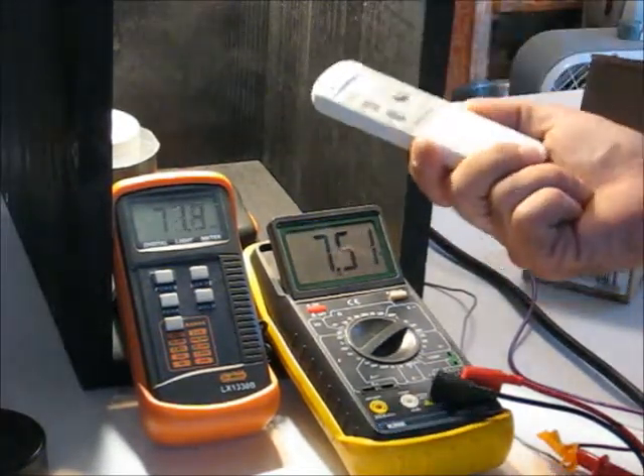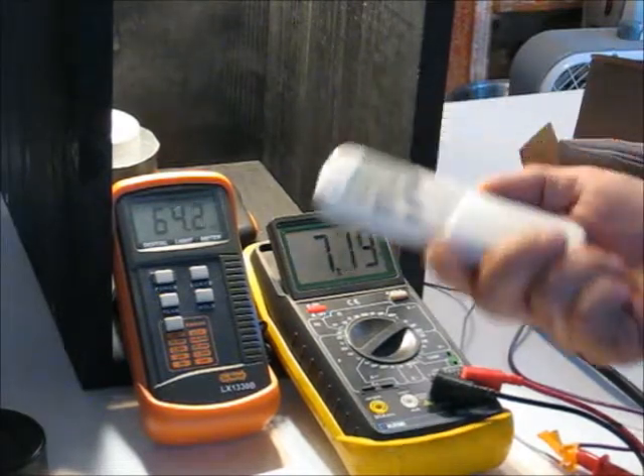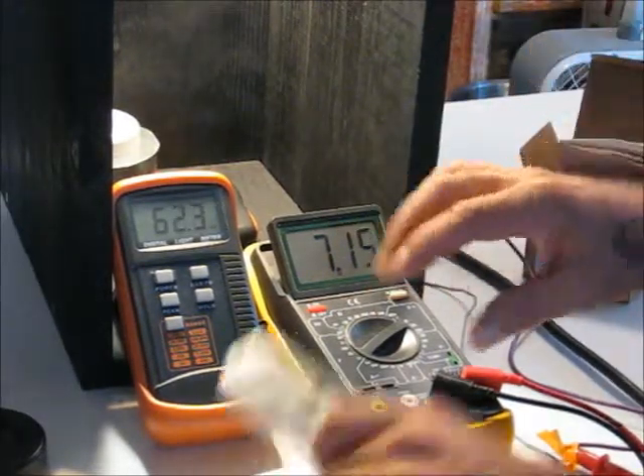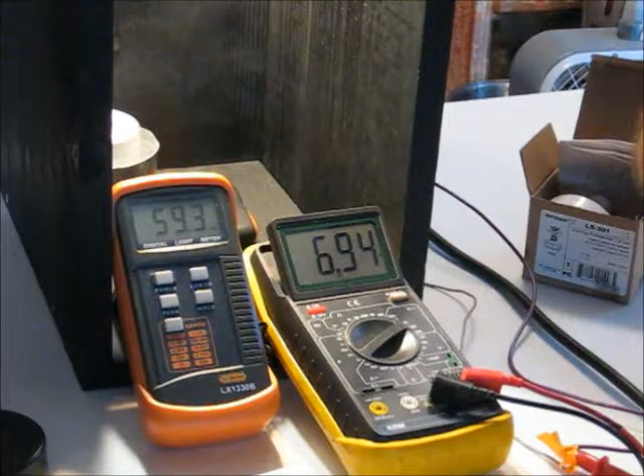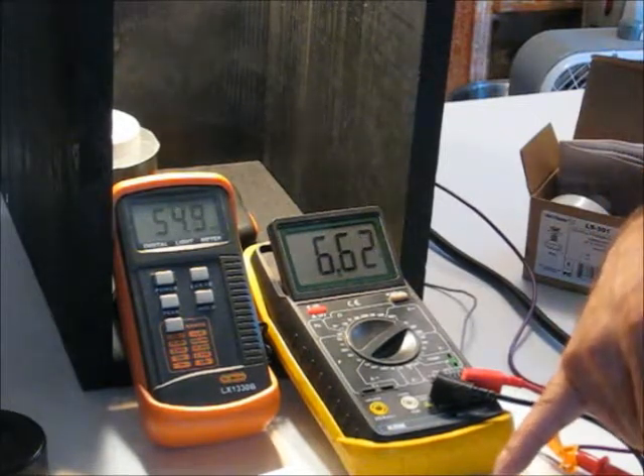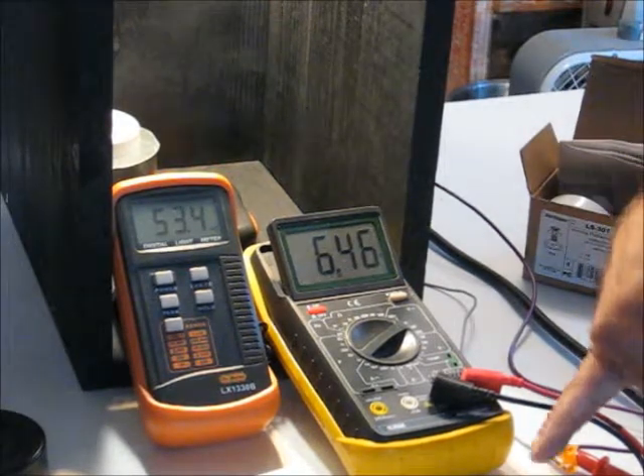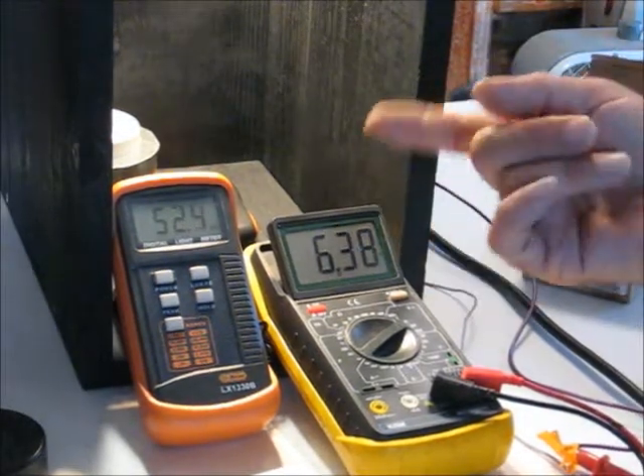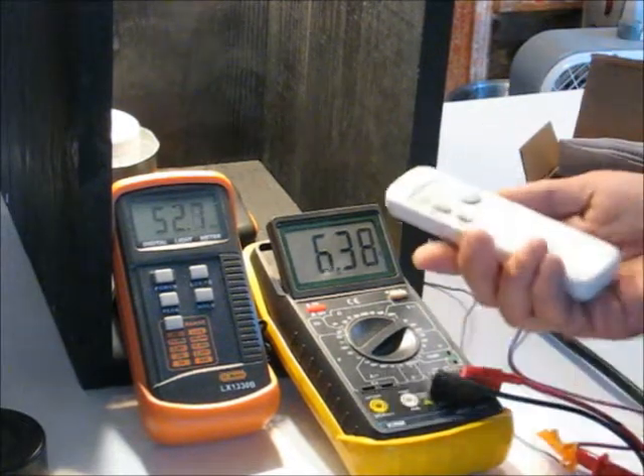Well, no. There's no acceptance test in the reference appendices, NA 7.6, addressing overriding of a daylighting system with a control. But if we look in section 130.1, it tells you that one control shall not override. And let me put this back in auto while I'm talking, bring it back down to 52. You can't override a control from one section of 130.1 with a control from another section in 130.1. As it turns out, there's some confusion now about the term override that needs to be clarified, but in my opinion, the ability to take the thing above set point and have it hang up there is out of code, but it doesn't violate acceptance testing criteria.